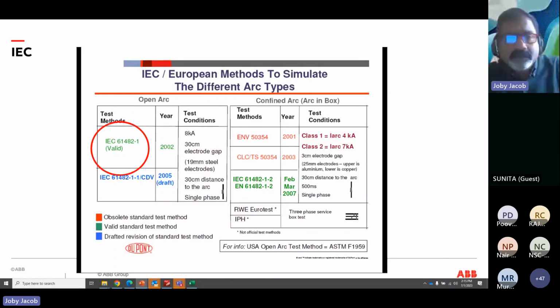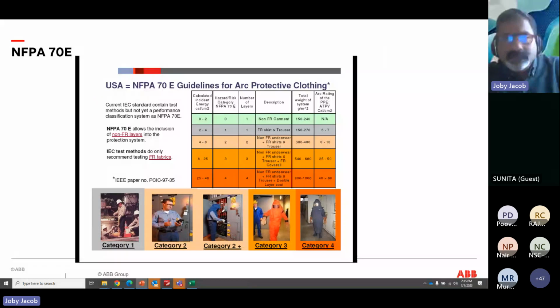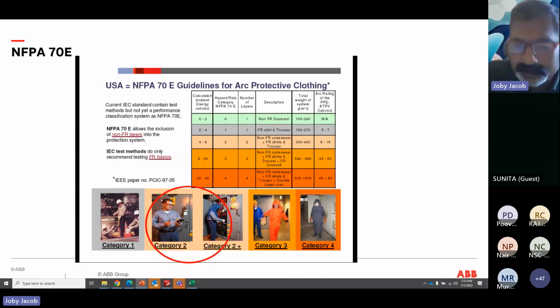And I don't want to go into detail on that. Actually, these are some of the tests you do, and these are the guidance as per the American standard NFPA 70E on the protection level coding. So there are several categories: Category 1, Category 2, Category 3, and Category 4. These are the categories we normally consider when you can wear a wearable type of PPE, right?